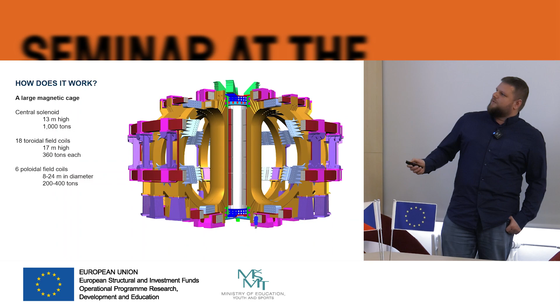Okay, let's move further. All of these elements which I showed you are confined inside the cryostat. The cryostat is basically the element which keeps the superconducting magnets that I showed before at a low enough temperature. They are cooled by liquid helium to 4.5 K. So, as far as I know, no superfluid helium is used there. This element is designed to provide a cold environment. Now, these holes that you can see here are called ports. These are access points into the vacuum vessel in which we put diagnostic equipment.